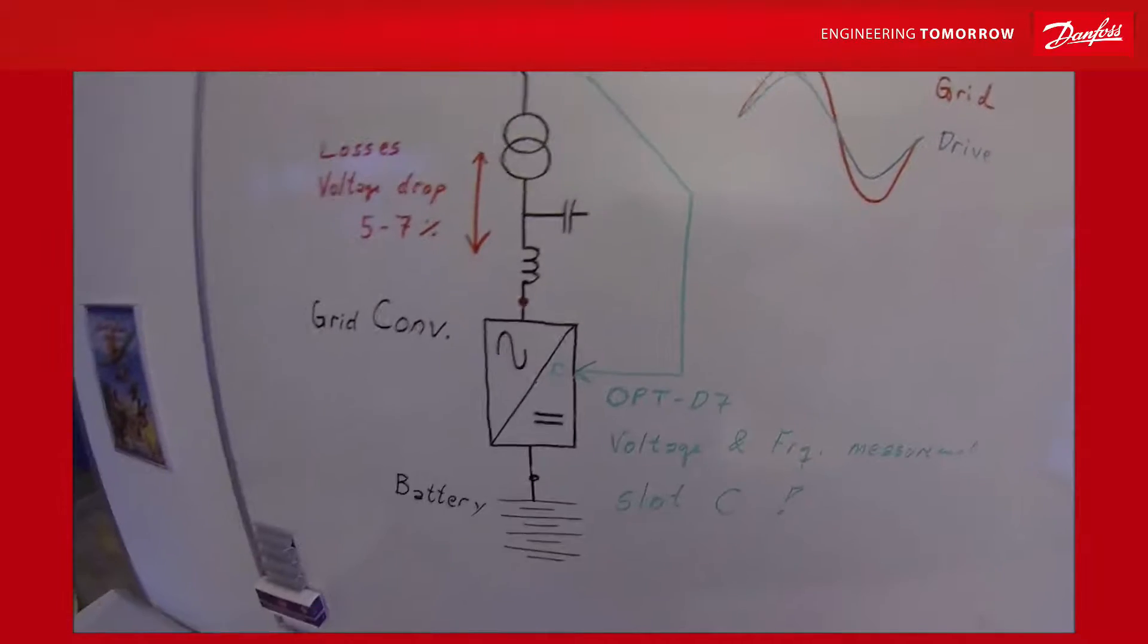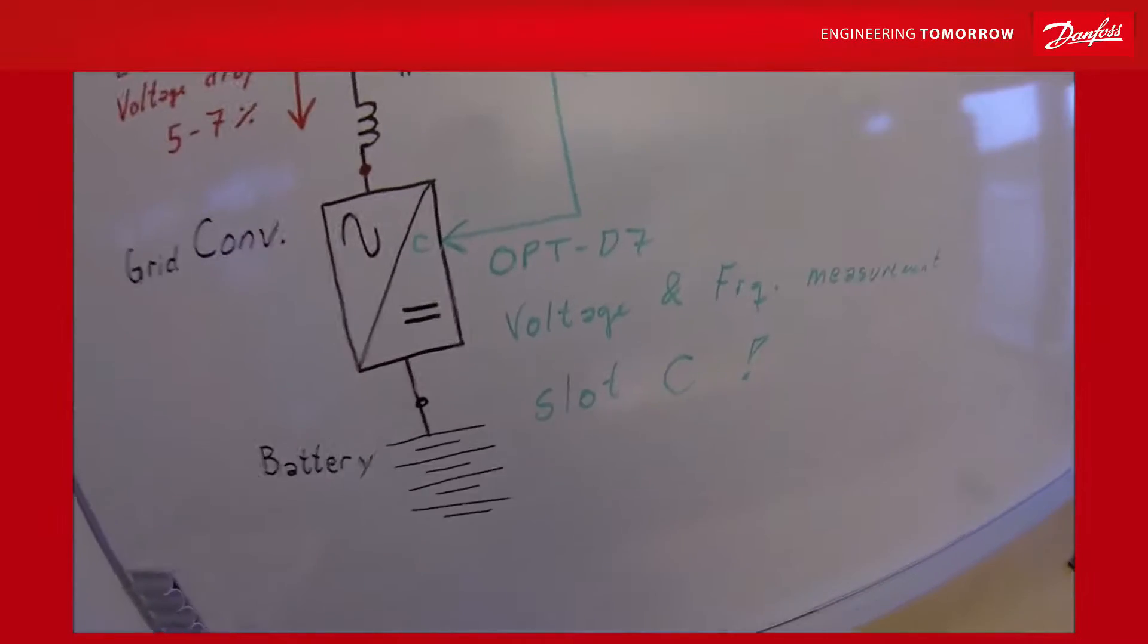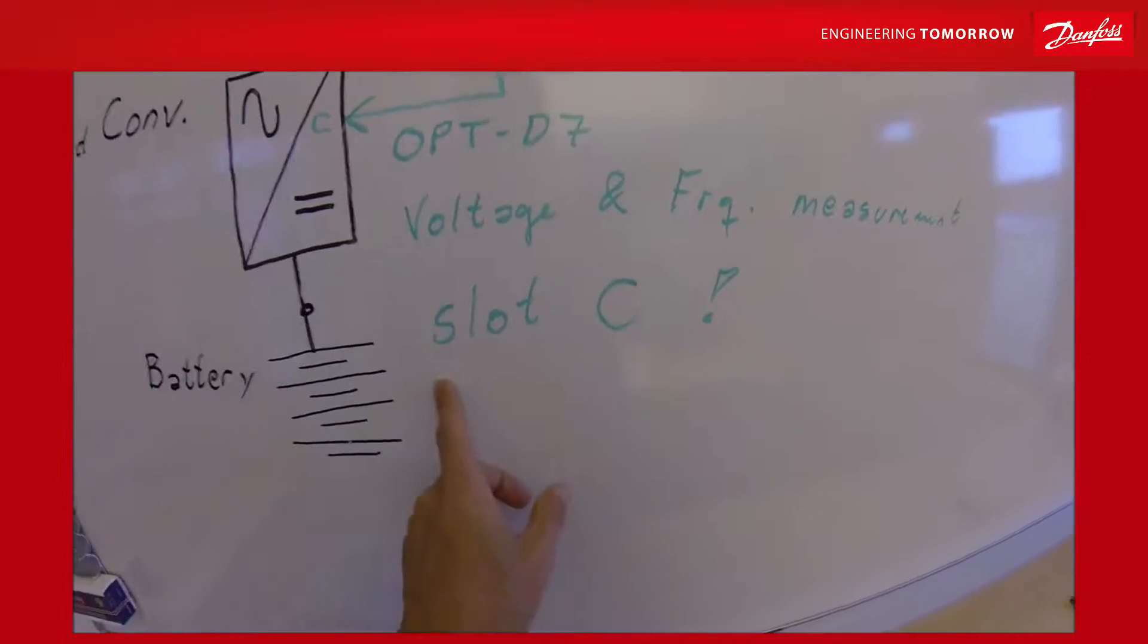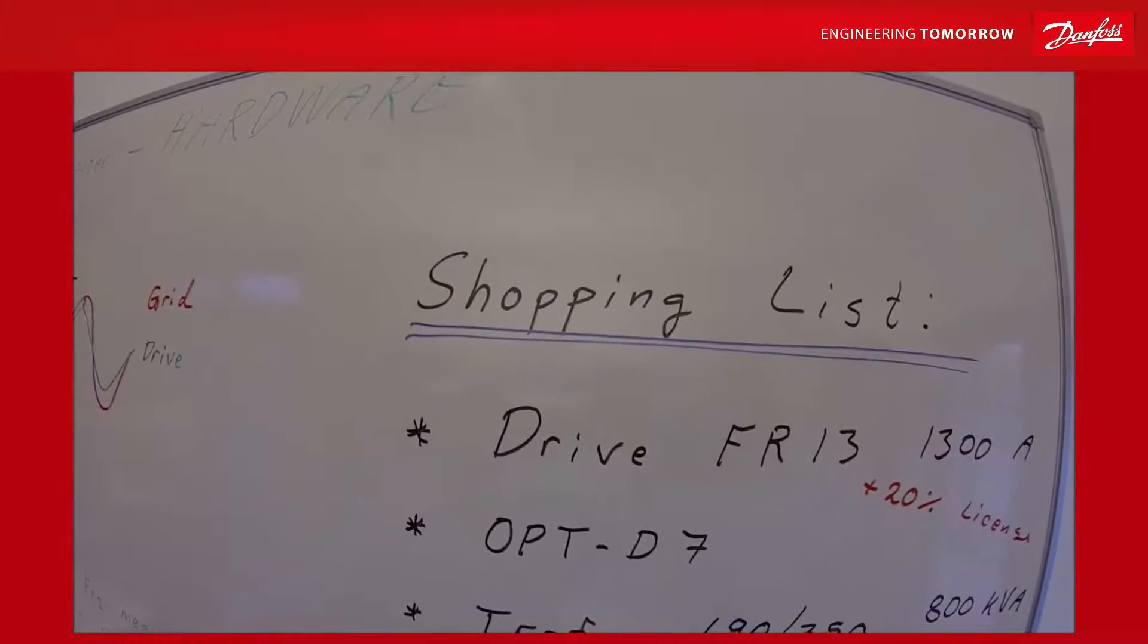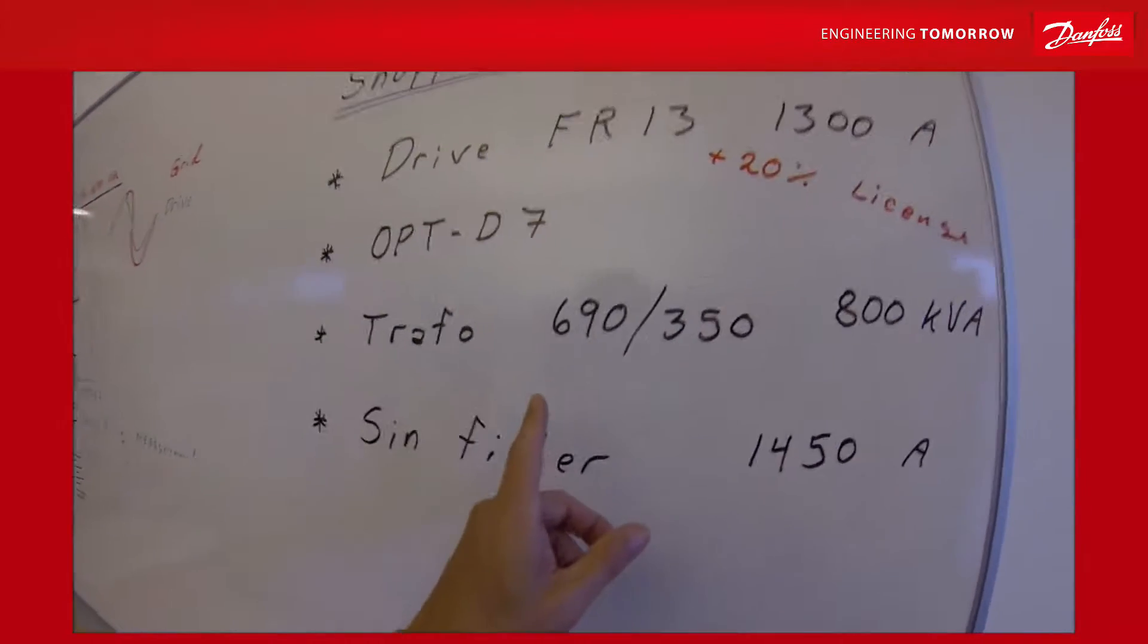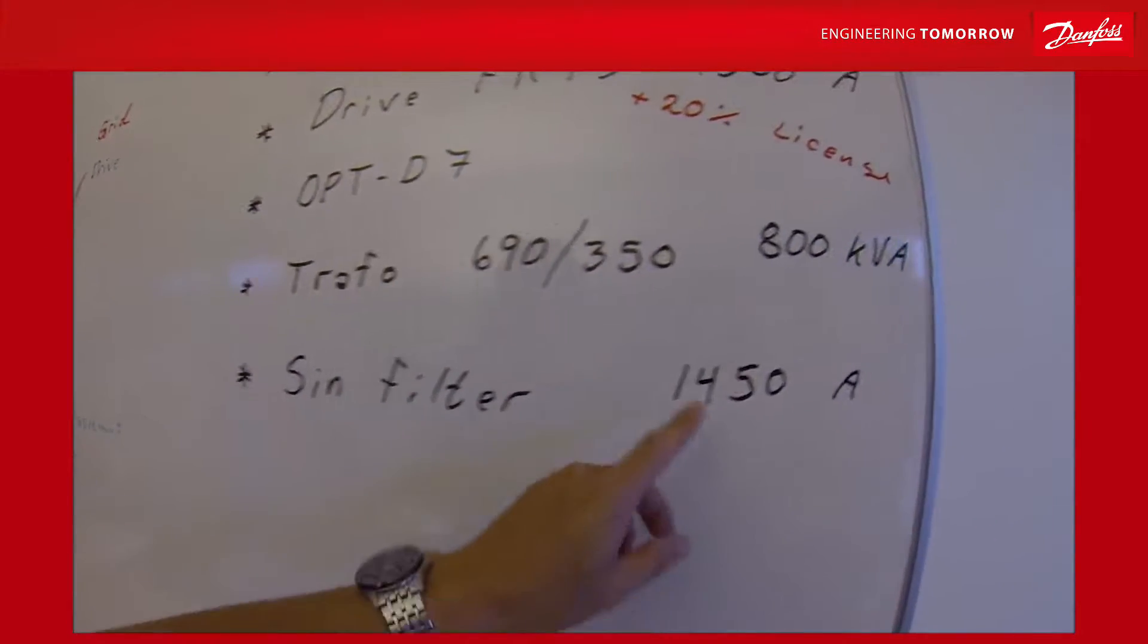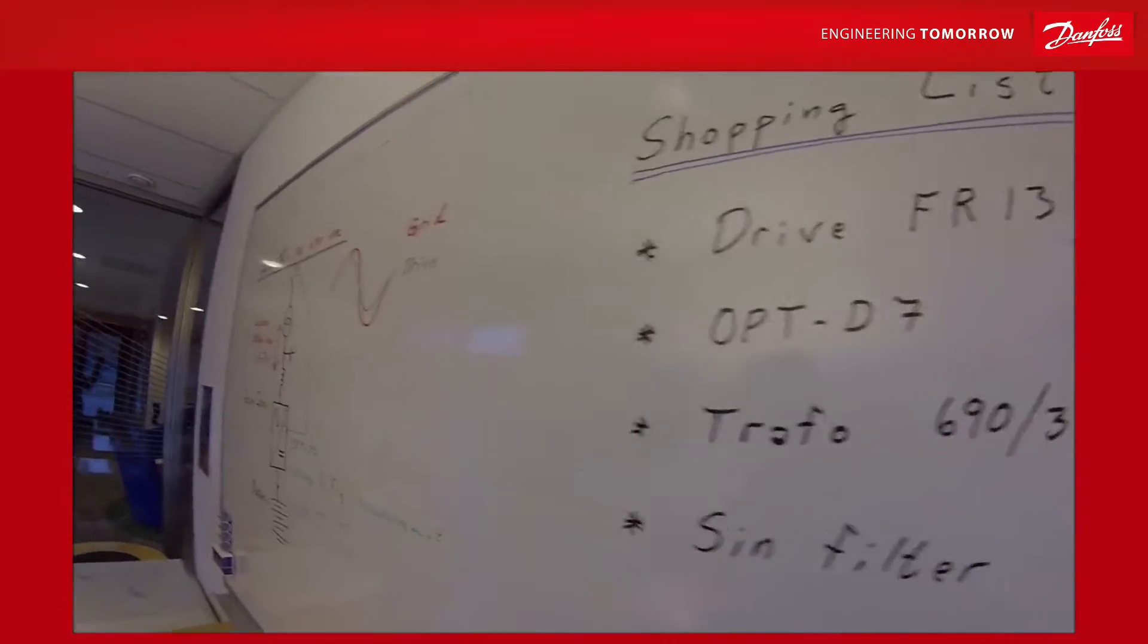Remember that in the drive you have to install the option board, the D7 board, and this can only be installed in slot C, which is the high speed measurement slot. The customer shopping list will then be our drive frame 13, 1300 ampere, plus the 20 percent license, the optional board D7, and the transformer should be 690 to 350, 800 kilovolt ampere, and a sine filter which goes to this drive, which is a 1450 ampere sine filter. That should be about what you need to make this drive. Thank you for watching.